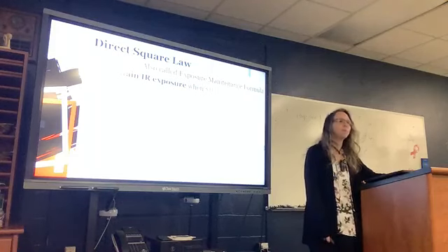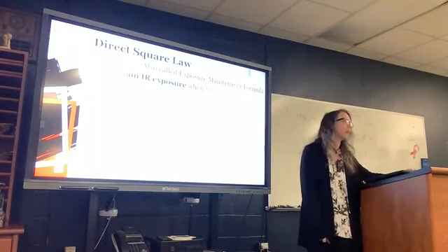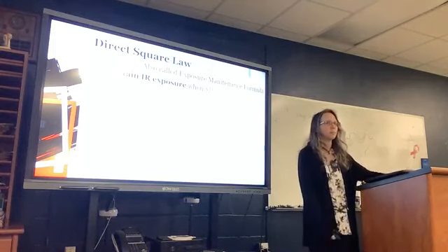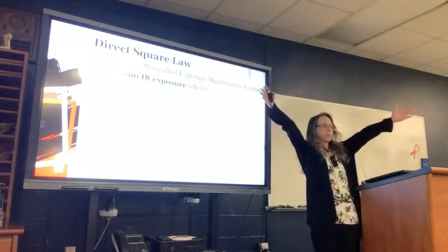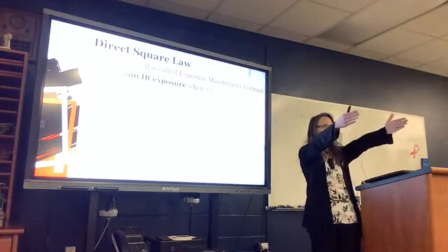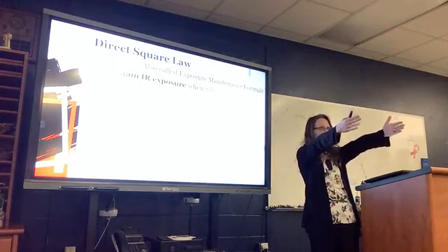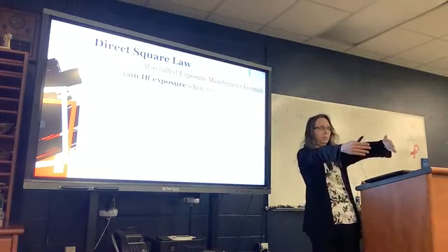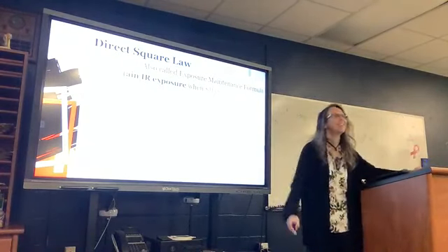If we go from 40 to 72, what happens to our light? It spreads out, right? And then we collimate to just the IR because we should not have light on the wall behind the patient. There's no need for that.